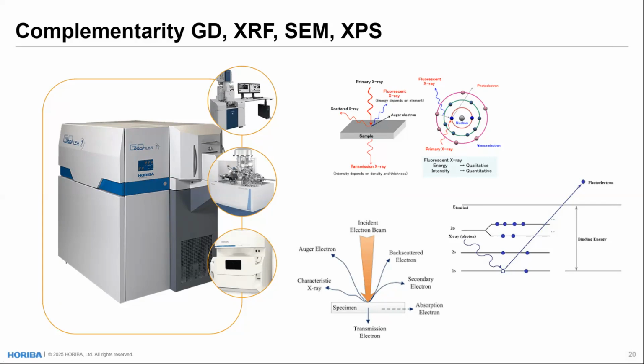Once the primary excitation beam hits the atom, it ejects an electron from the core and creates a vacancy. An electron from a higher shell jumps to the vacancy and creates characteristic X-rays. The energy of each level, K, L, M, is unique for each element, so we have a unique spectrum, a unique fingerprint, for any element. Later you can see the characteristic K line and L line.